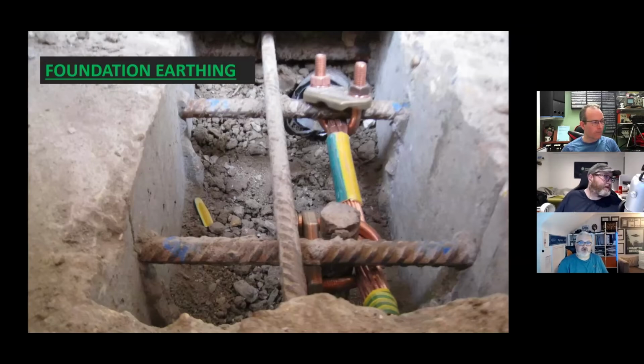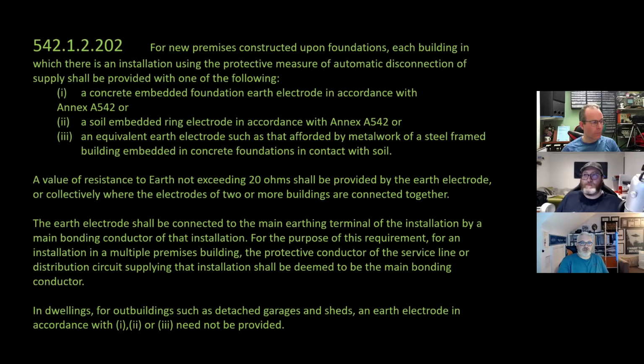Drum roll. You can tell by the picture, foundation earthing. So this is something I was doing 12 years ago. There is a new regulation. It's a UK specific regulation, and it states, for new premises constructed upon foundations, each building in which there is an installation using the protective measure of ADS, formerly known as EEBADS, shall be provided with one of the following: a concrete embedded foundation earth electrode in accordance with Annex A542, or a soil embedded ring electrode in accordance with Annex A542, or an equivalent earth electrode such as that afforded by metalwork of a steel framed building embedded in concrete foundations in contact with soil.